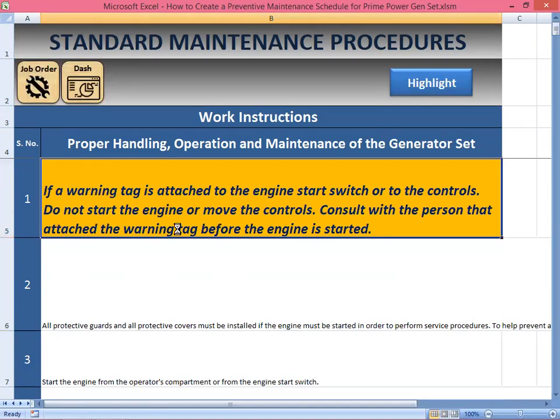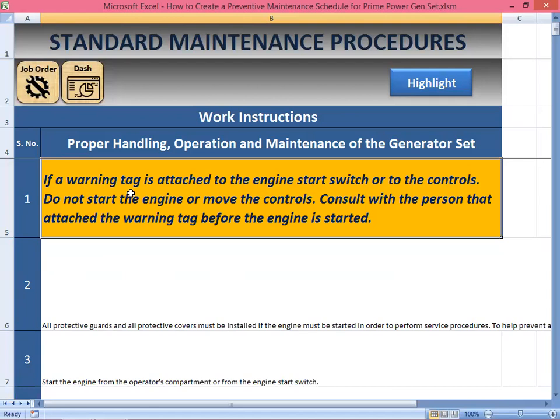What are the things that we're going to be avoiding here? We avoid accidents, incidents, physical injuries. We avoid fire hazards. We avoid damaging the unit or the asset. So we have to make sure that these procedures are implemented. The first one: if a warning tag is attached to the engine start switch or to the controls, do not start the engine. Do not remove the tag; consult with the person that attached the warning tag before the engine is started. There may be other workers working in the control panels, the switchboards, or other equipment remote from the generator set.